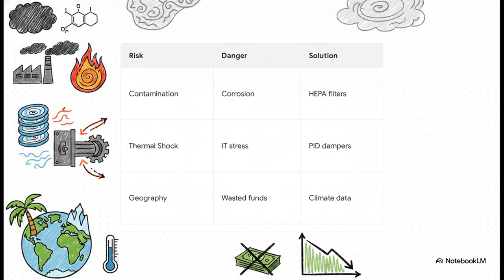First up, contamination. Imagine a nearby factory venting toxic gas or a forest fire blowing smoke your way. That can get sucked directly into the server room, causing rapid chemical corrosion. The fix: multi-layered HEPA and intense chemical filters.